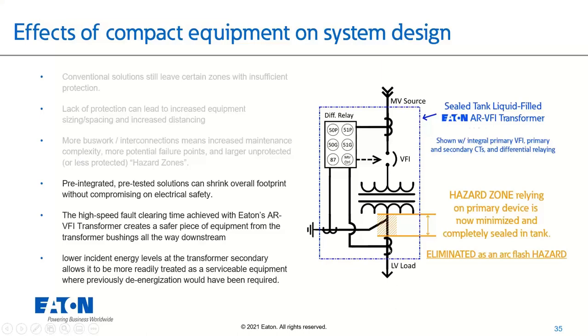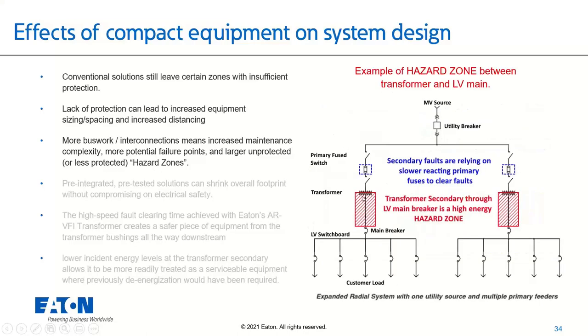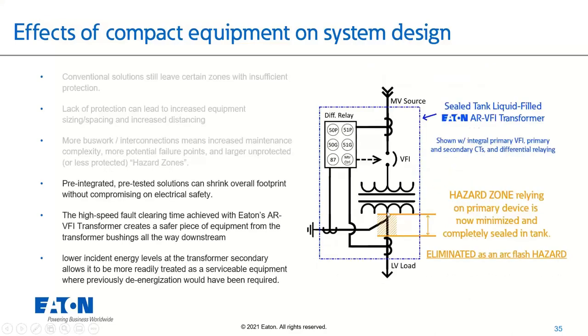And we've now taken what was essentially the zone between the transformer secondary and the sensing of the main breaker, that very large hazard zone, and shrunk it to between the transformer secondary and the set of CTs. This is all in tank. And now it's eliminated as an arc flash hazard altogether because it's completely out of the way of the user. It's a sealed-in-tank environment.